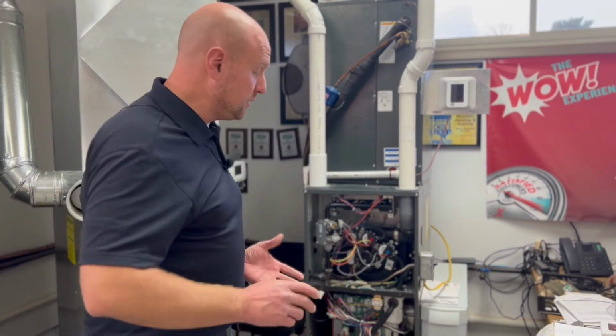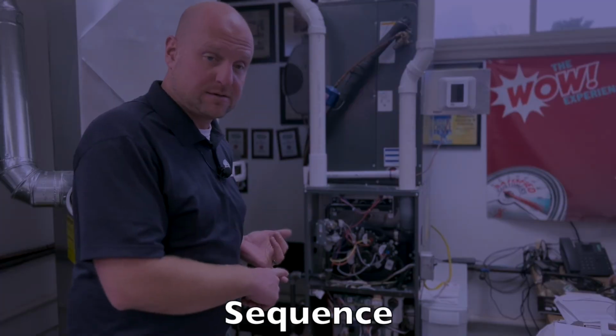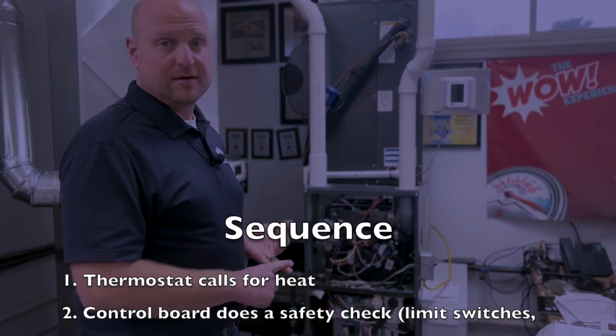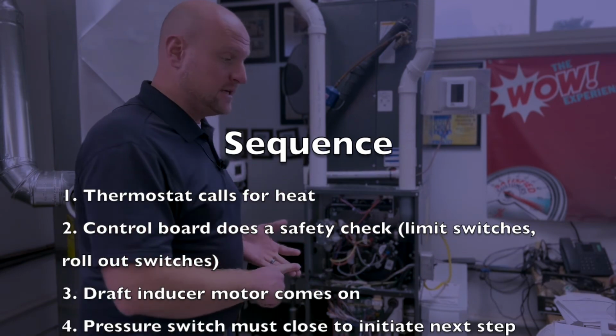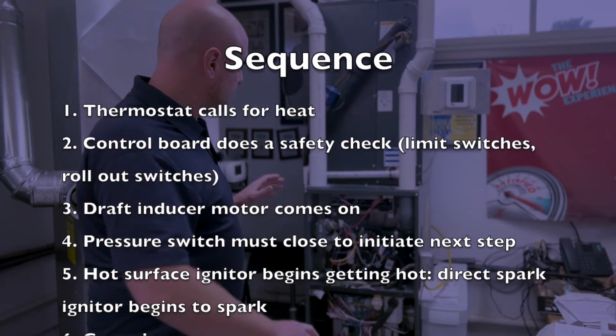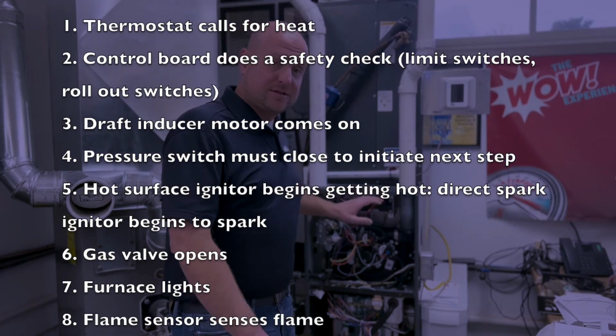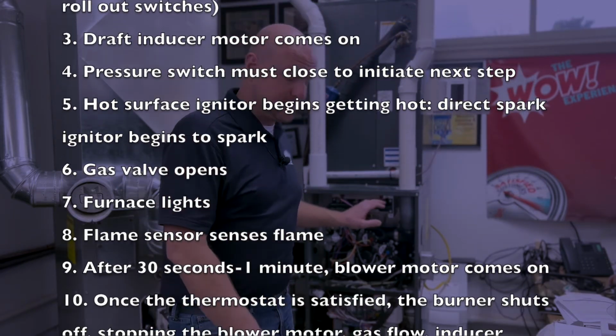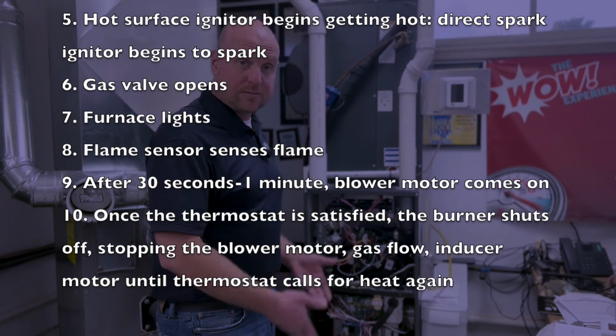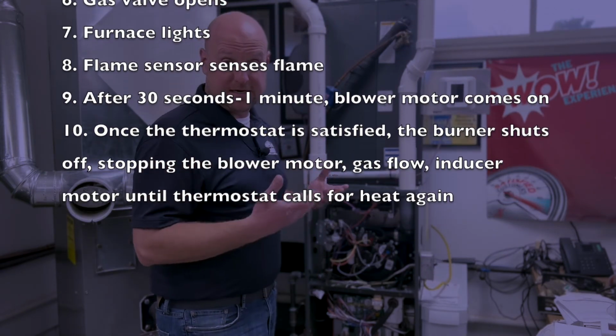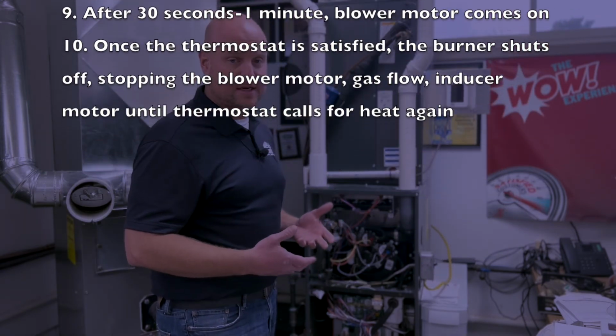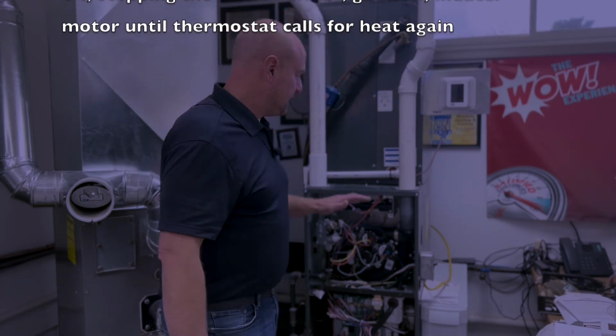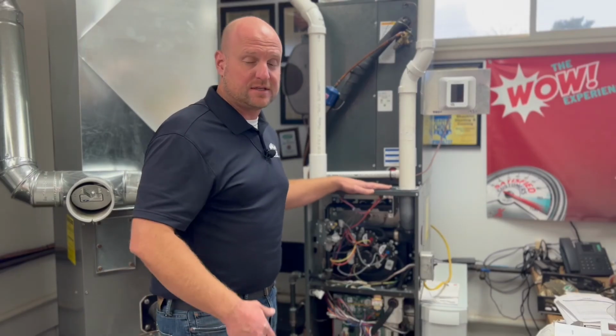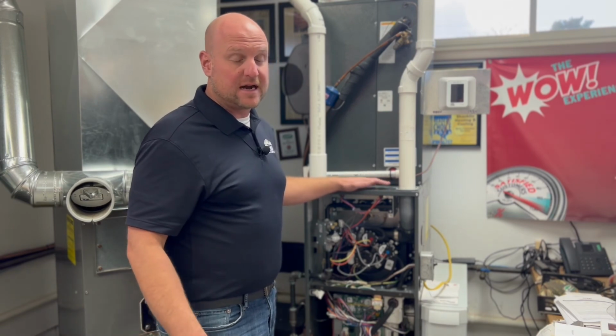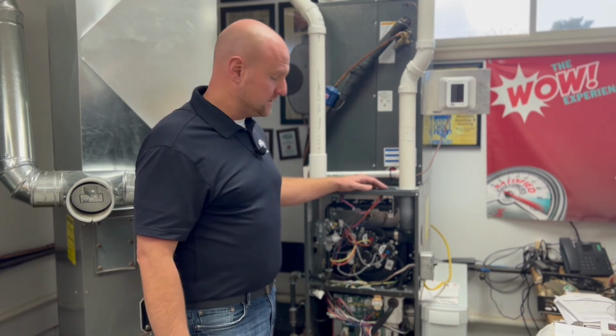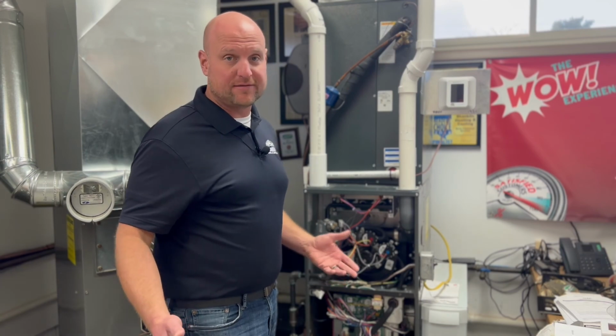So let's recap real quickly. Thermostat calls, turns the draft inducer on. The pressure switch proves it. The igniter turns on. The gas valve opens. The flame sensor proves or disproves the flame and sends it back down. The blower motor turns on to start heating the home. Very important to realize this process. It's a very linear process. Even though this is a 96% furnace, many of the other furnaces out there operate in a very similar way. So this is the sequence of operation of a natural gas furnace.